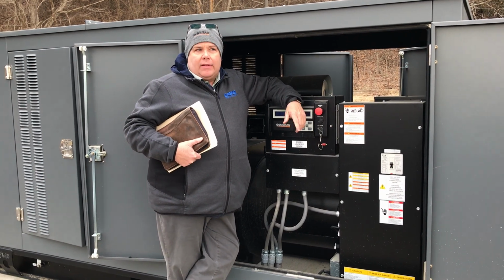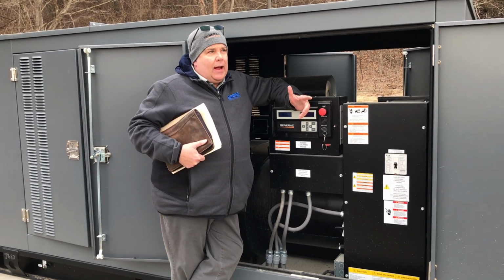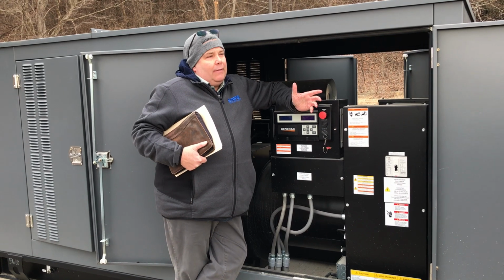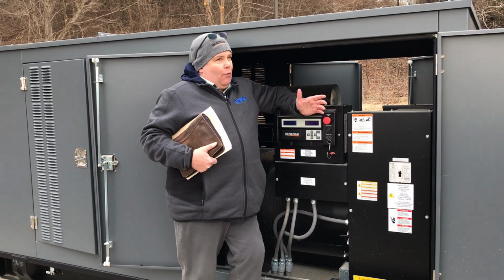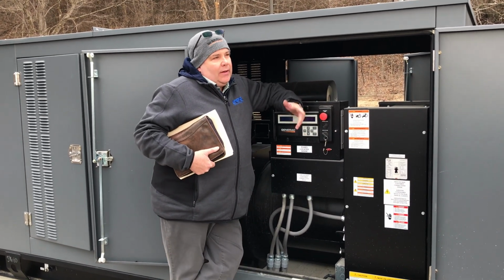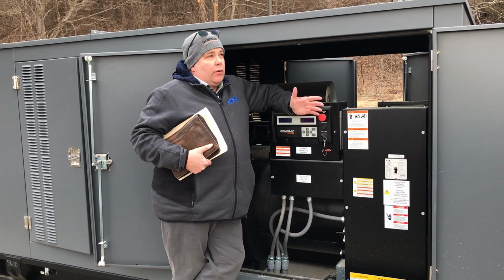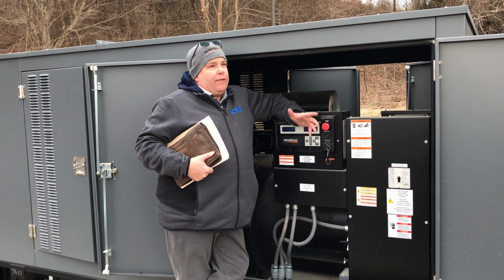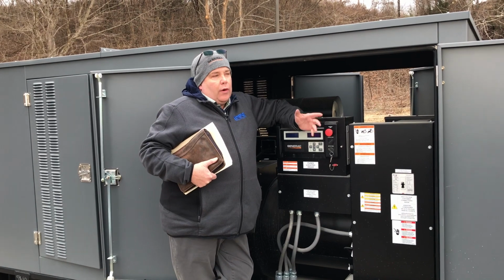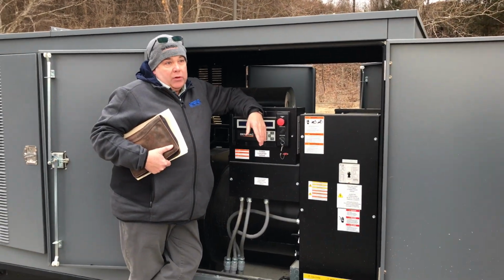A load bank is the best way to do it. A lot of the time, the correct building load may only be 30, 40, 50%. Like in hospitals, if the load's only 30%, they have to load bank them almost every month.